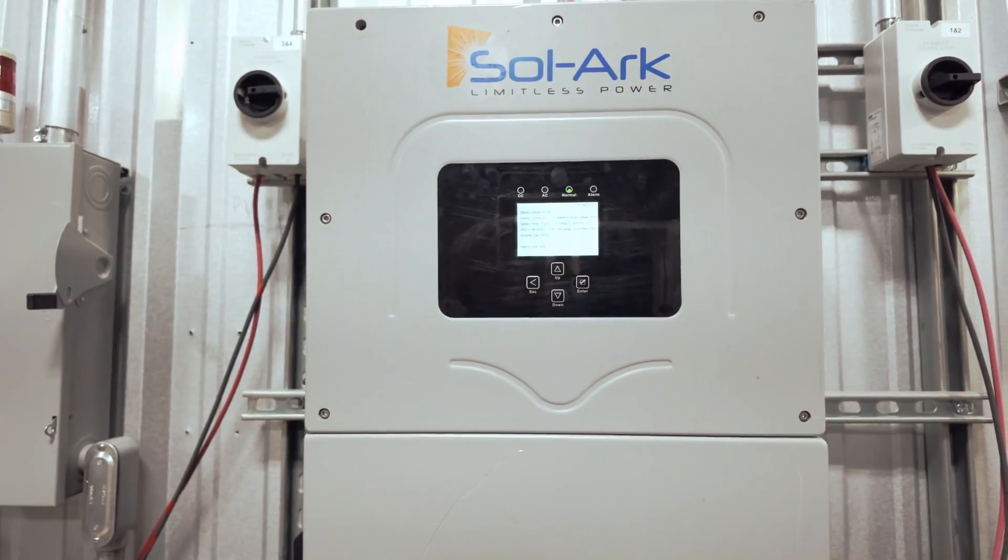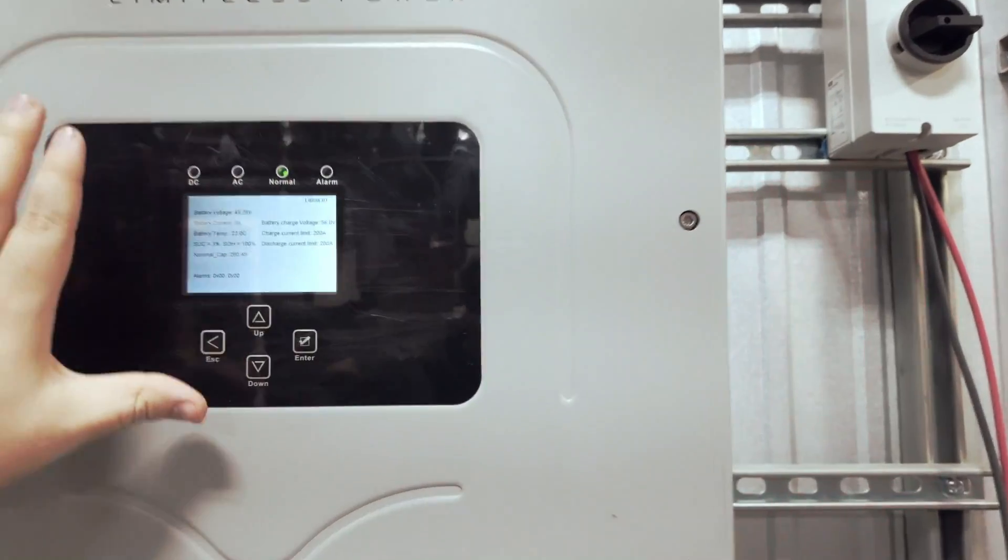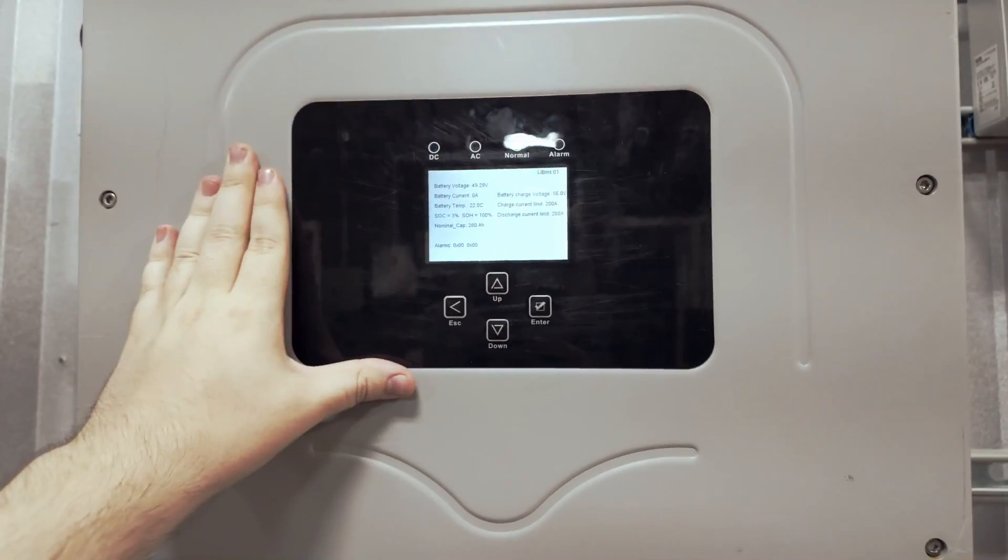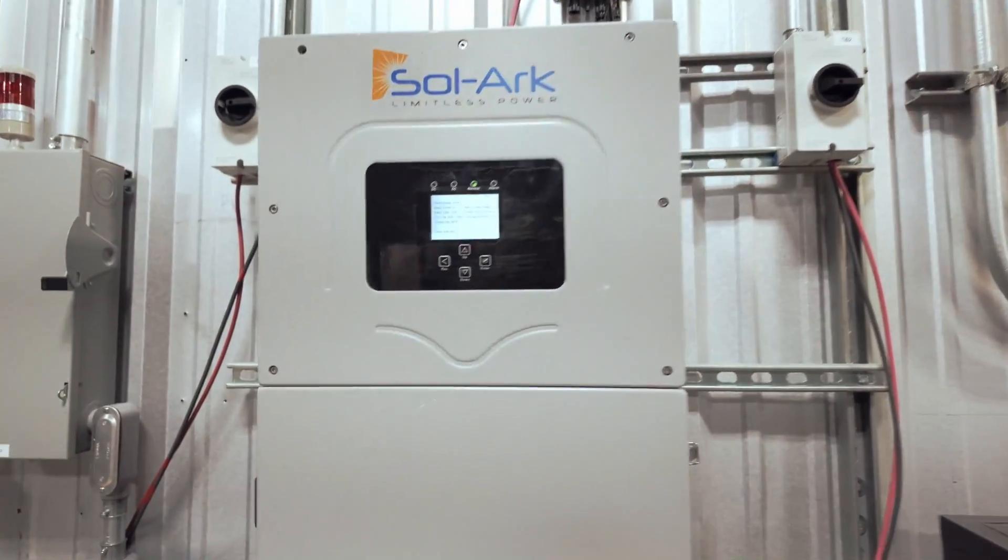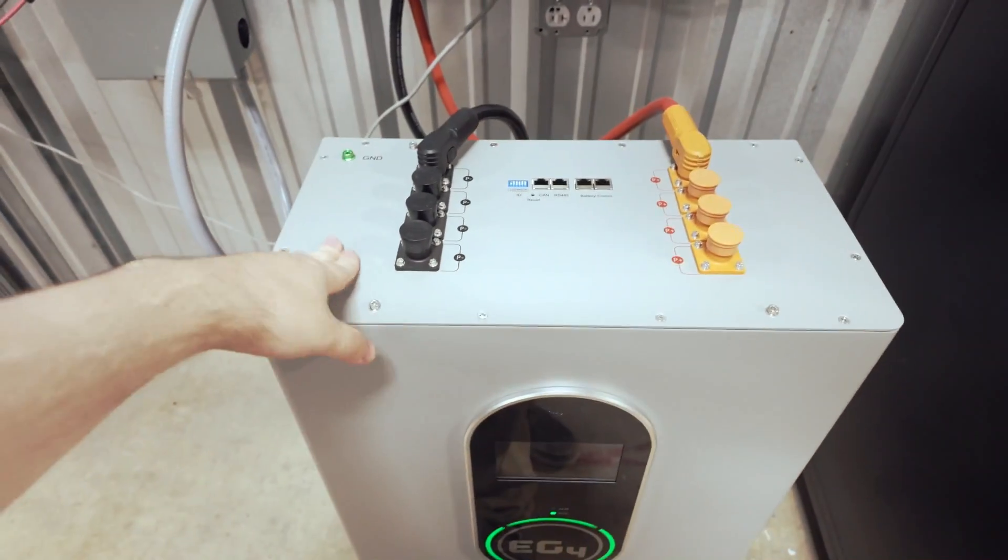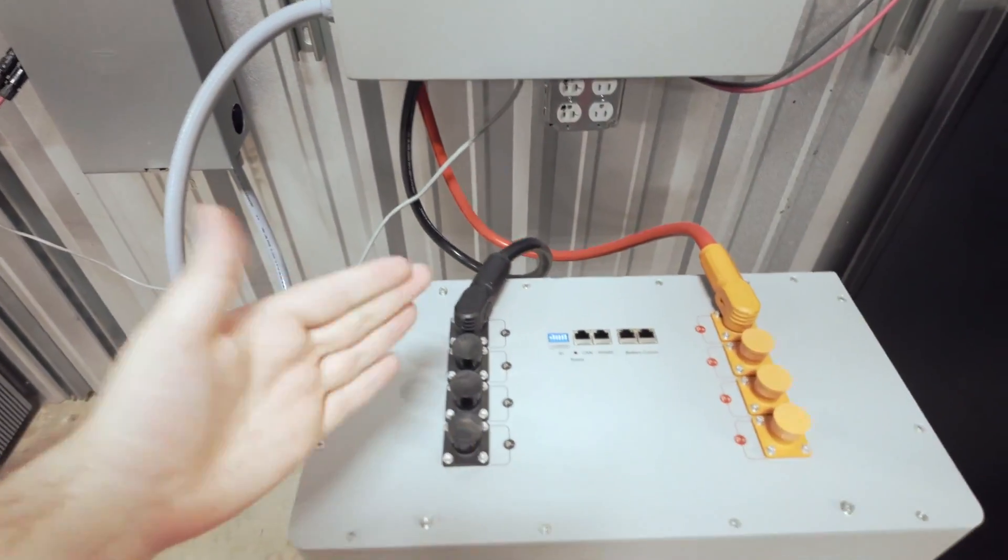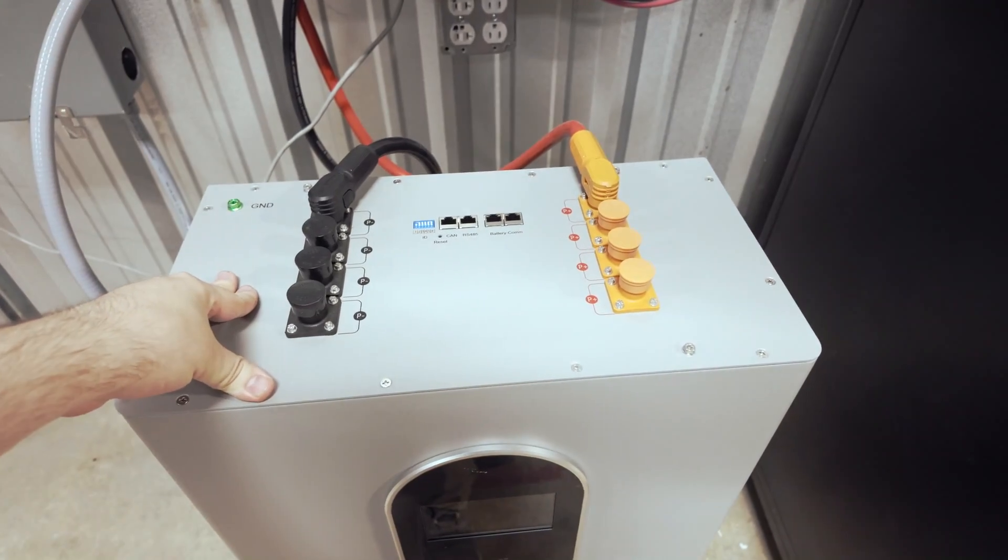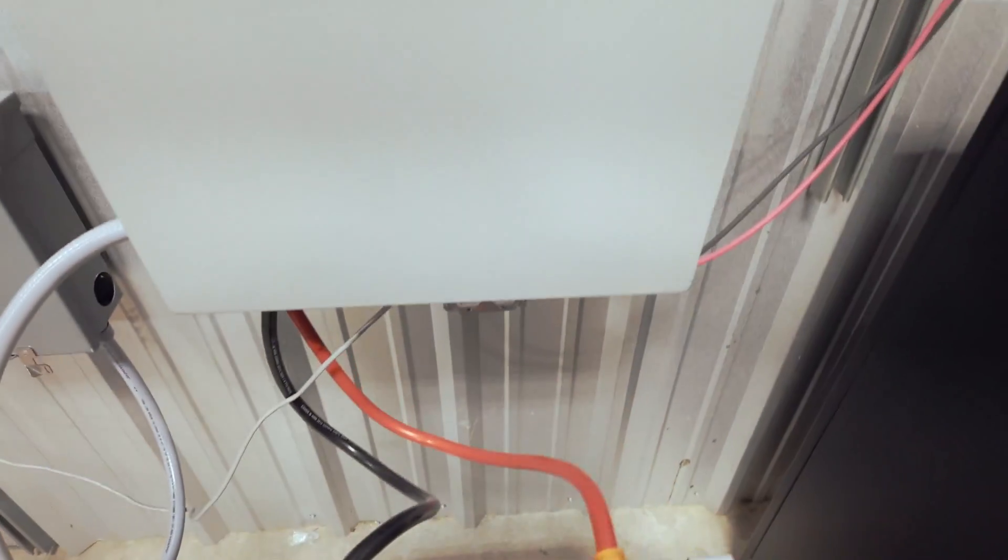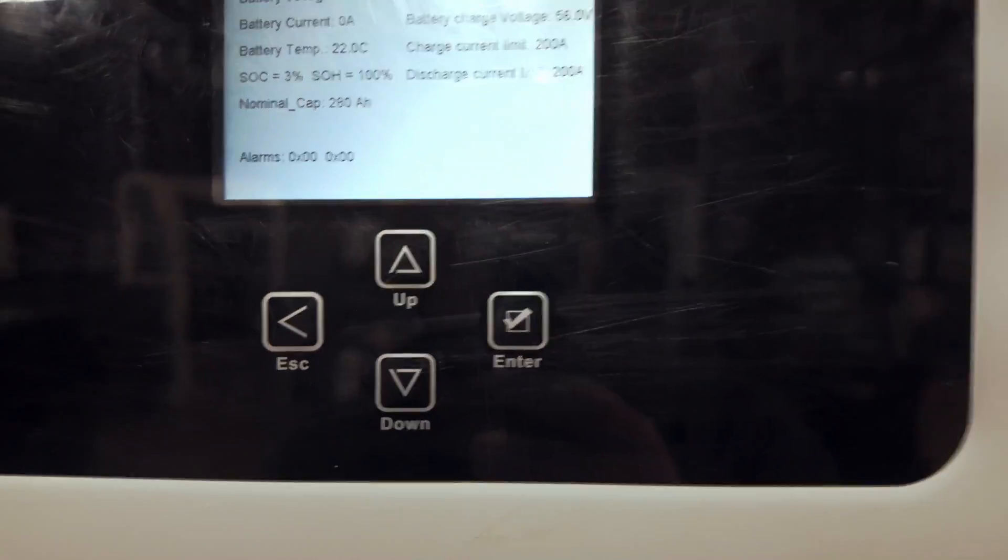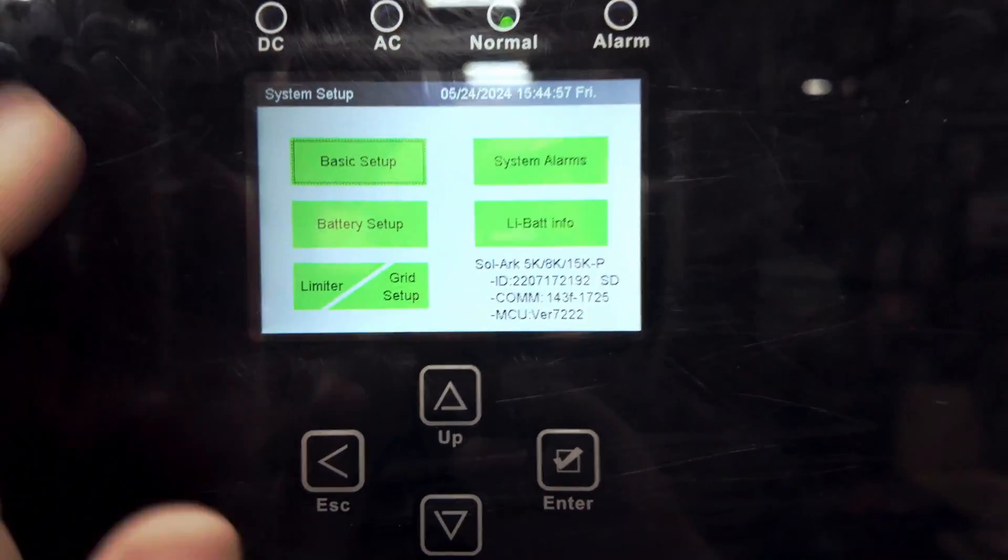It's important to note that with a single wall mount battery, your Solark's charge and discharge outputs from the battery will be limited to about 10 kilowatts instead of 12 because the 200 amp BMS on the batteries does put that limit down as far as the maximum output that it can output. So it's important to note that if you're not able to get full maximum capacity from output of your Solark.